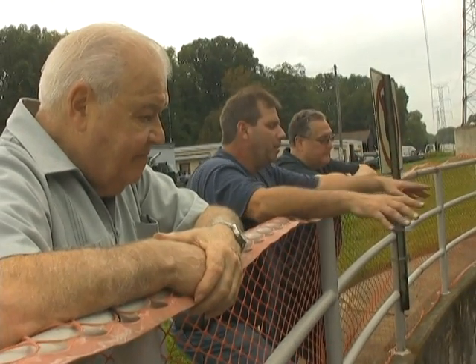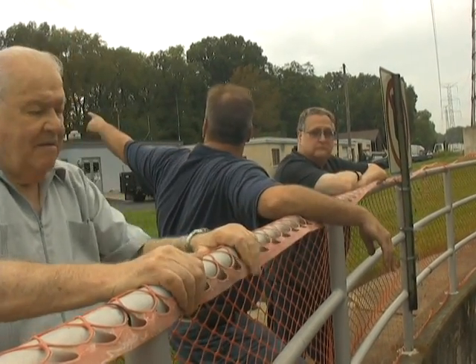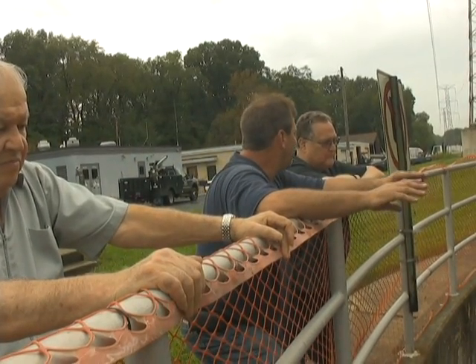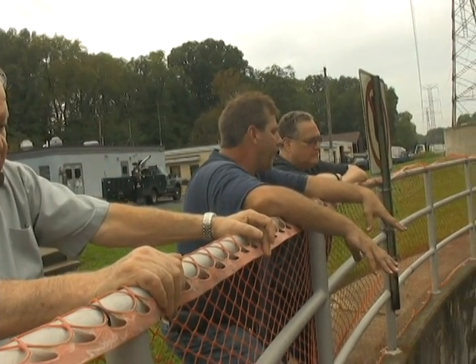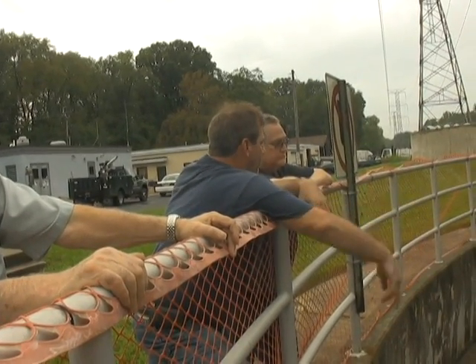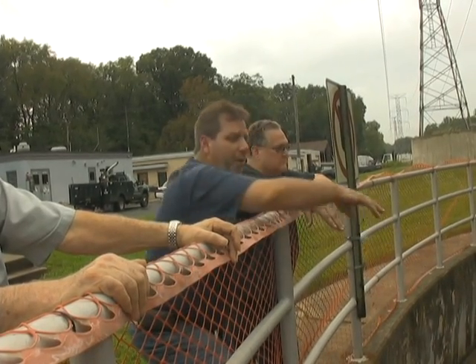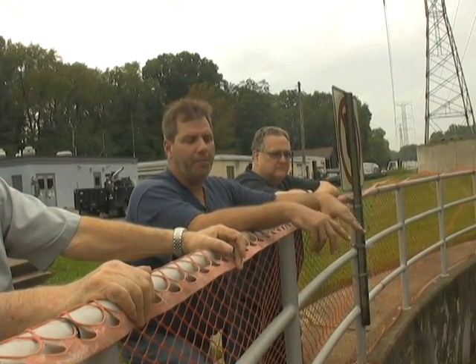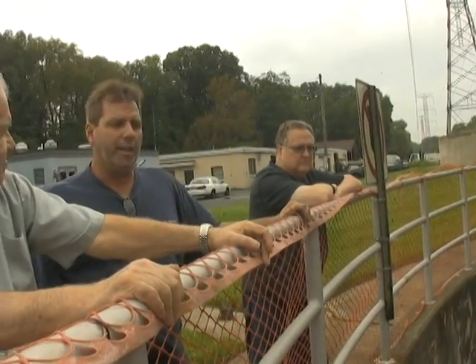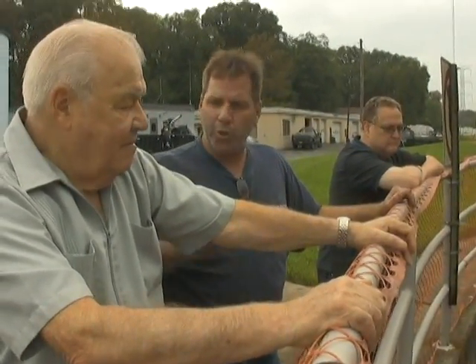Oh, okay. And then what would happen is, if this tank is filled, this is the same kind of tank that's in the middle, but you have a lot less solids. So the refined solids will settle to the bottom. The rake arms will bring it into that hopper, and then that sludge is sent back to the head of the plant. If we do redo the tank, I'm thinking about keeping this half filled up, and then when we're going to get a wet weather event, drain it back down.